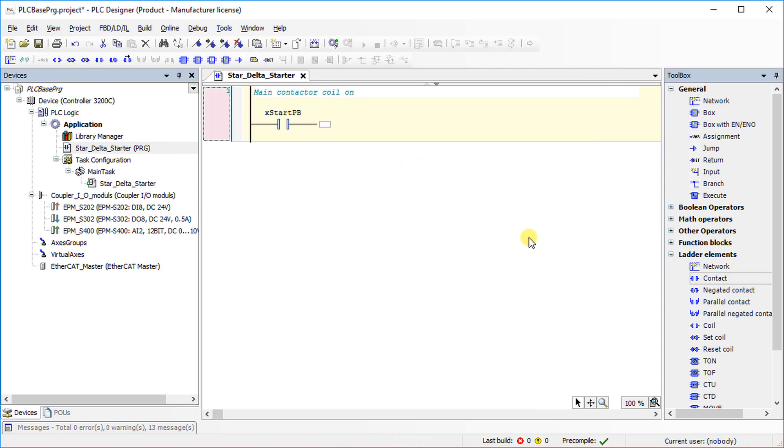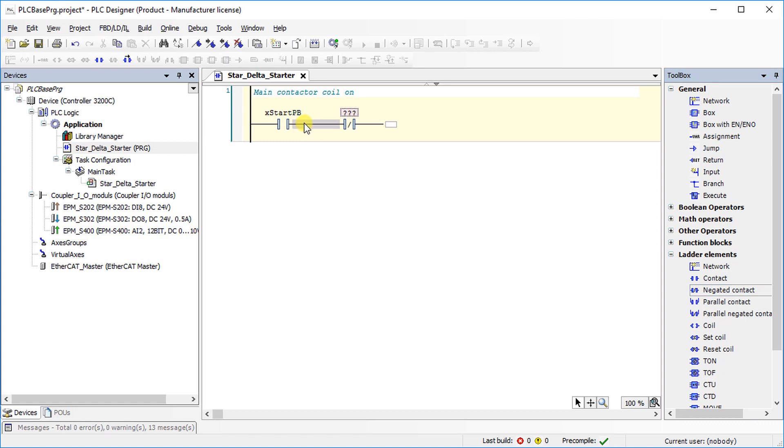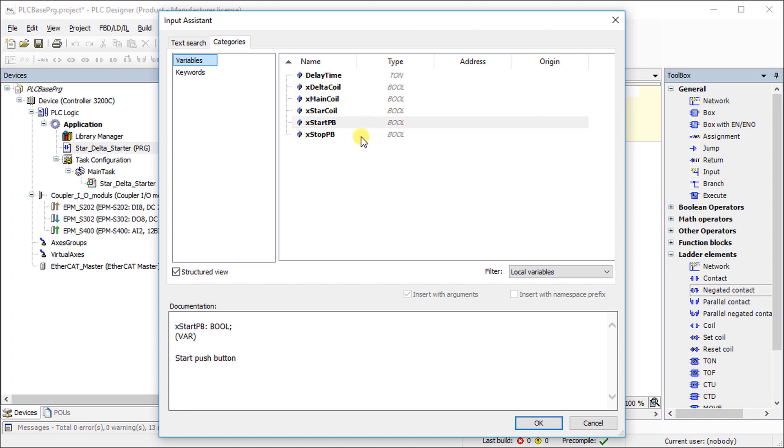For stop push button, choose negated contact. Drag and link it to the start push button in series. In this example, assume the stop push button has a normally closed contact. That is why, in ladder diagram, negated contact for stop push button needs to be selected. Choose stop push button input using input assistant.